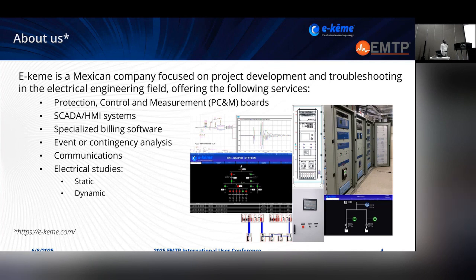We also develop some SCADA and HMI solutions integrating modern communication protocols. And this enables us to monitor in real time the variables in substations and load centers. We have also specialized billing software, and this specialized billing software not only gives us the tariffs that CFE applies to customers, but it can also give control actions with an HMI integrated to this software. In other cases, we have also made some event and contingency analysis for our clients. We use some oscillography events and SCADA logs to analyze the root cause of the problem.